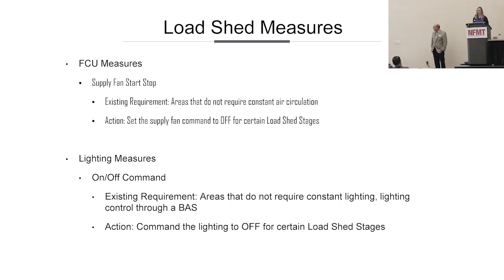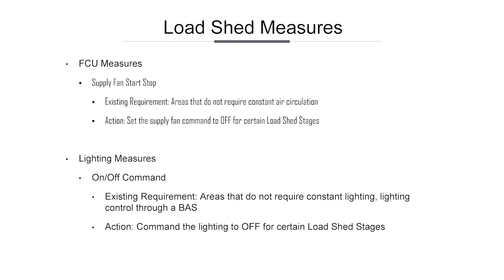And then the lighting, that was really for stage 5, but we had hallways where if we really needed to cut that load, then we were shutting off the corridors or the hallways, shutting the lights off. And at first, people did wonder, why are the lights going off in the middle of the day if it really needed to do stage 5? And after they learned what was going on, no one really cared because they were in their office and they can deal with a little bit of less light going through the hallway to the restroom.